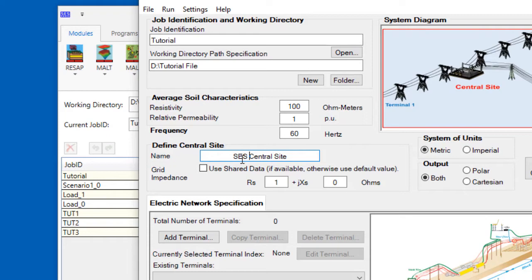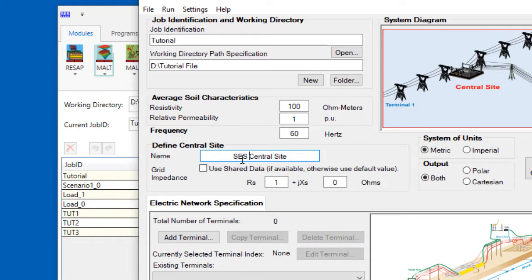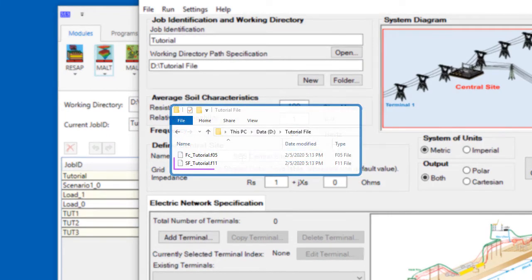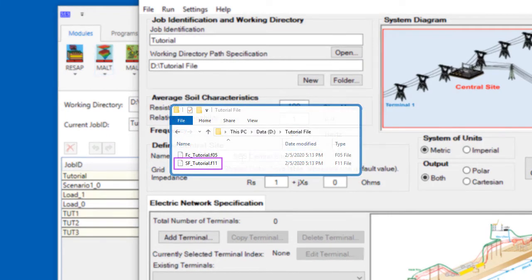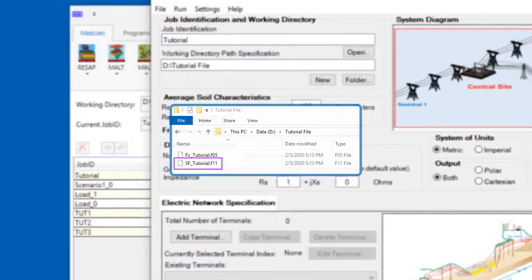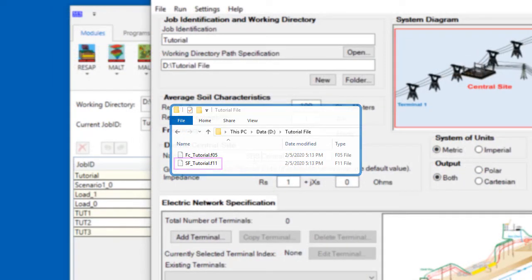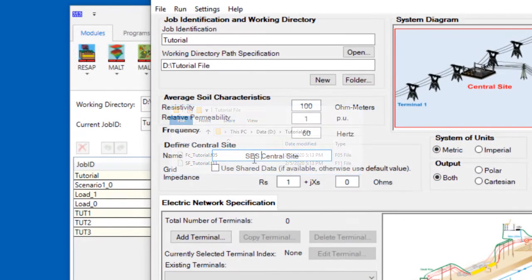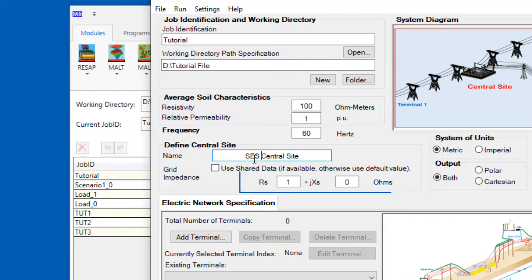For example, if you previously used MALT to compute the resistance of your grounding grid, then MALT would have created a file with an F11 extension. This is called a share file, and FCDIST would be able to use the resistance value in that share file. Or, if you previously computed the impedance of your grid with MALZ or HIFREQ, then you can manually enter that grid impedance value here.